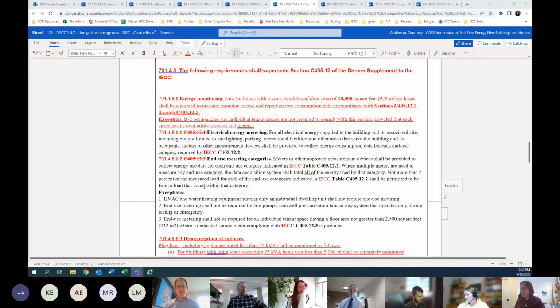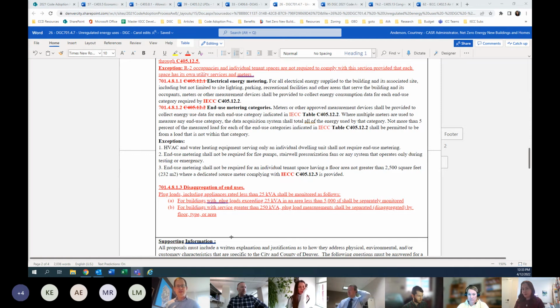If you scroll down a little towards disaggregation—this just adds more detail to require disaggregation of end uses, such that plug loads and appliances rated less than 25 kVA shall be separately monitored, and that buildings with service greater than 250 kVA shall have plug load measurements separated or disaggregated by floor type or area. This is related to plug loads but also to monitoring feedback. It's a step, if you will, towards an outcome-based code, enabling a better feedback loop to get data on what's happening in the building, so performance can be maintained over its life.